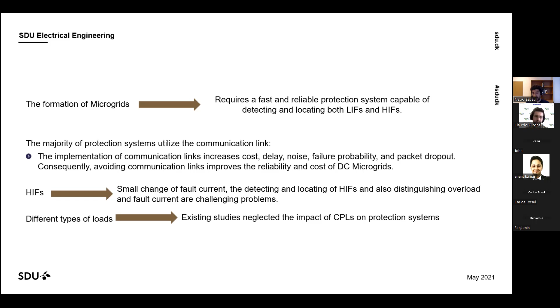And also in DC microgrids, because DC microgrids are special microgrids, it's really hard to avoid the impact of loads. Normally in a power system, we avoid the impact of load on the protection, because loads cannot participate much in the fault and the protection. But here in DC microgrids, because we are talking about, for example, data centers, their behavior during the fault is different. So we have different challenges in protecting microgrids.